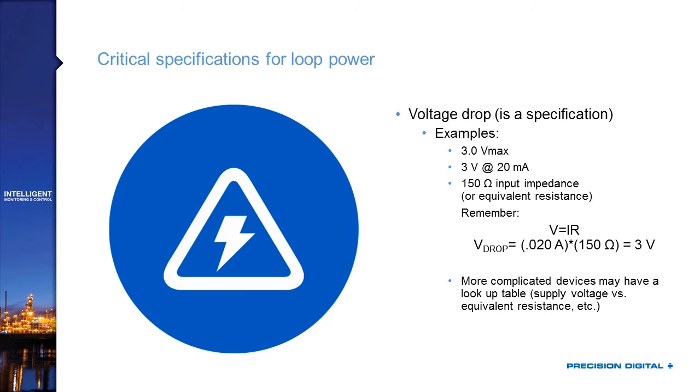Examples of how that voltage drop might appear are listed here. You have like 3.0 volts max. Okay, well that's telling me that my device has a 3 volt maximum drop on that loop. You might see 3 volts at 20 milliamps. Well, the maximum voltage drop is going to occur at the highest current level. So for a 4 to 20 milliamp loop, that means 20 milliamps. So 3 volts at 20 milliamps is telling me the same thing.